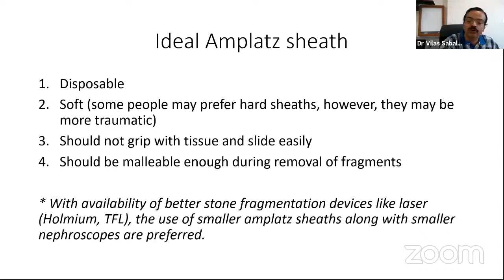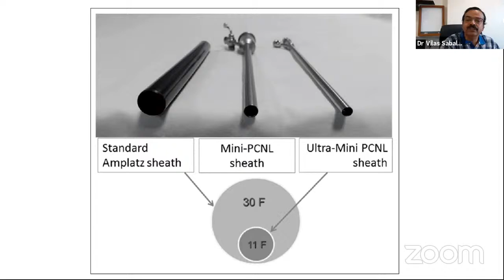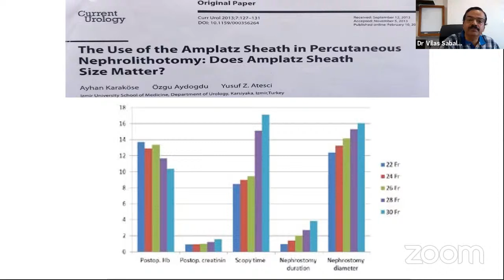With the availability of better devices, which you have learned over the last 2 hours, like holmium laser, thulium fiber laser, smaller and smaller Amplatz sheaths with smaller and smaller nephroscopes are being used for PCNL with a lot of advantages. This was the initial standard 30 French Amplatz sheath, and we have an ultra mini PCNL of 11 French metallic sheaths, and mini perc XS much smaller than that also. This is one study where they compared the Amplatz sheath diameter and various complications like blood loss, hospital stay, nephrostomy tube size, and the smaller Amplatz sheath has proved effective in a variety of ways to reduce the blood loss. Then the nephrostomy size also reduces, the hospital stay reduces, but at times for a larger stone, the larger sheath can be useful to reduce the operative time and get larger fragments much more frequently and easily.